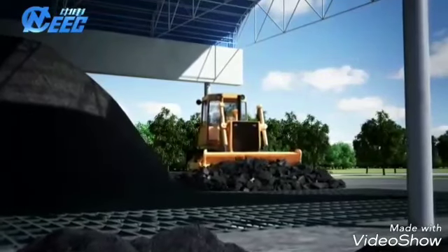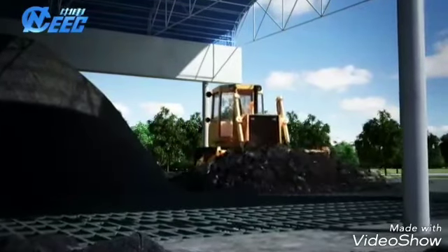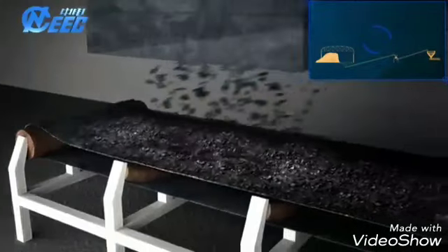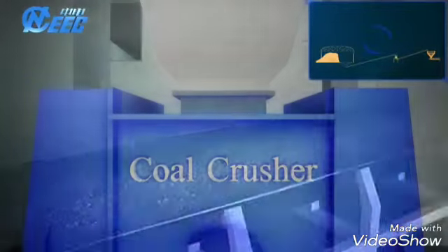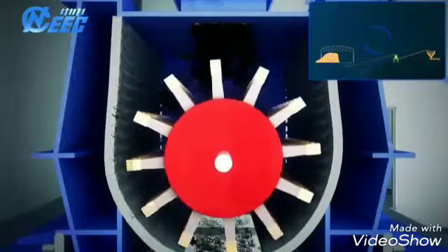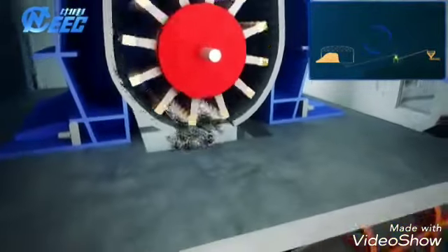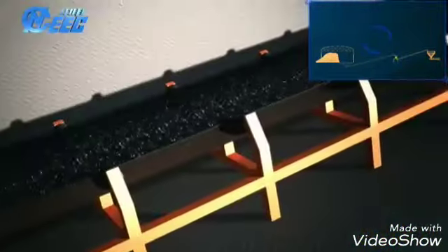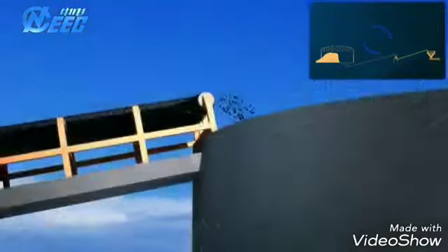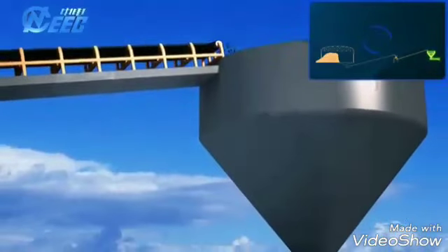A coal dozer is pushing raw coal into the ditch. Raw coal in the ditch is lifted into crusher by conveyor belt. Raw coal is crushed into powder, finest at 0.1 to 5 millimeters. Coal powder is conveyed into raw coal hopper for storage.